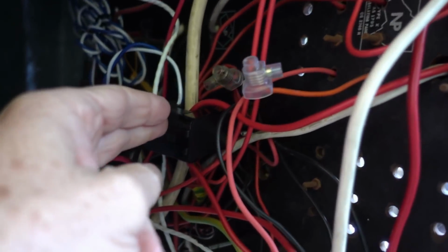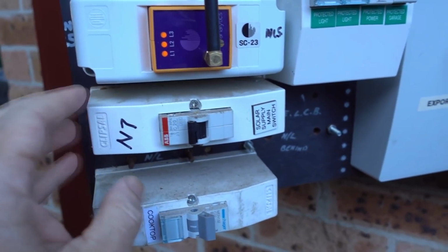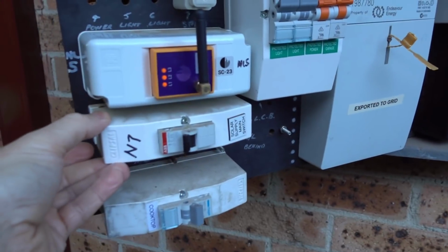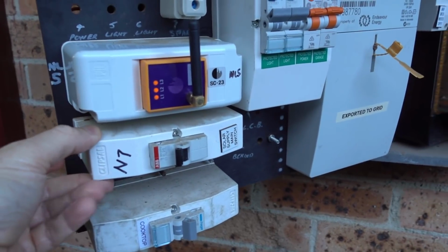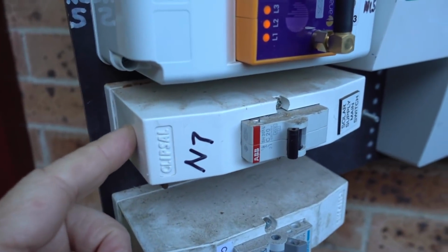So it's still there, but what we want to do is actually subtract what's coming from the old 3 kilowatt system, because it doesn't know about this. This Envoy system, all it knows about is the 5 kilowatts coming from here. So anything extra put in by any additional solar panels, we have to actually subtract. And the way you do that is, you can see, hopefully, that I've got an extra wire running through there like that. And if you follow the money, follow it down, it actually goes into here, and that is the main switch for the 3 kilowatt system.